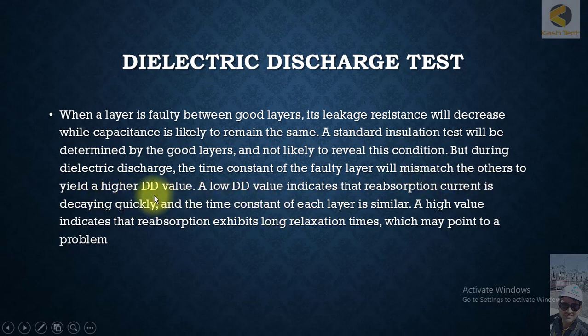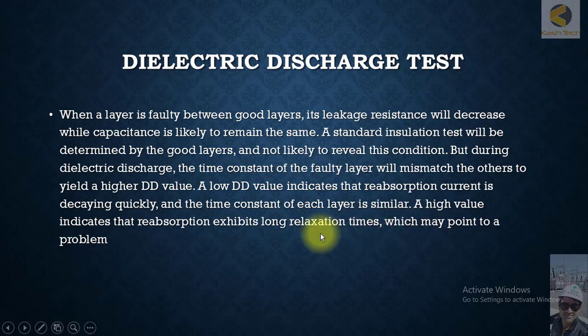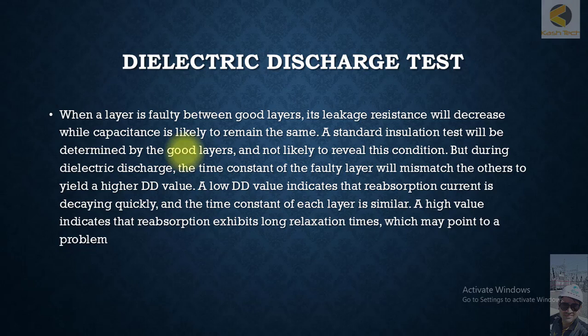A standard insulation test will be determined by the good layers and is not likely to reveal a faulty condition. But during dielectric discharge, the time constant of the fault layer will mismatch the others to yield a higher dielectric discharge value. A low DDD value indicates that reabsorption current is decaying quickly and the time constant of each layer is similar. A higher value indicates that reabsorption exhibits long relaxation times, which may point to a problem. If one or two layers are defective, you will see a different pattern, and you can find out that the insulation is defective — but normal insulation testing could not find this issue.